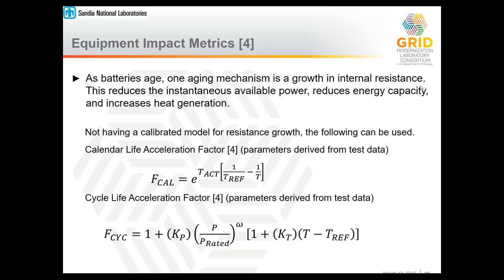Here's the slide where that goes. Maybe a first approximation, but obviously if you have a specific chemistry that you're looking at, you would do some research and figure out the life acceleration factors for that device. Or you would work with a specific manufacturer to ask what their life acceleration factor is, and you would use that in your model. A lot of times battery manufacturers would be pretty reticent to supply that because that's some of their secret sauce, so it's not necessarily something you would have access to. Where that is the case, I would almost suggest not using it. But for a first approximation, this was provided in reference 4, which is a vehicle battery test manual for life verification. Without a calibrated model, this one's pretty good.